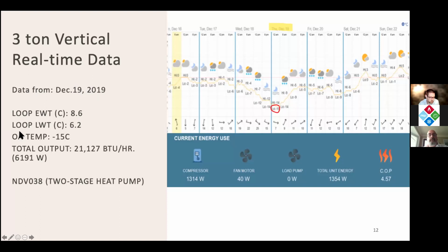On this particular day, the outdoor air temperature was minus 15 Celsius, and the load or the output from the heat pump itself was about 21,000 BTUs. And this is a 3-ton ground source heat pump, and I believe a 2-stage heat pump. So here we can see, this isn't the coldest day of the year, but this is minus 15. We were running a COP of 4.5. So that's a pretty incredible performance figure right there.